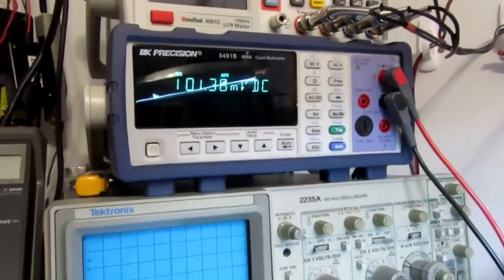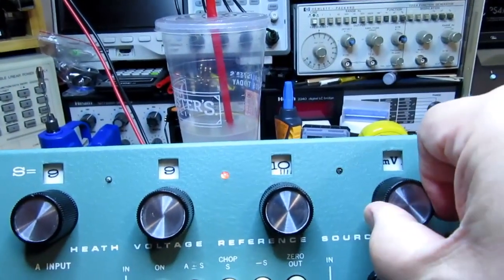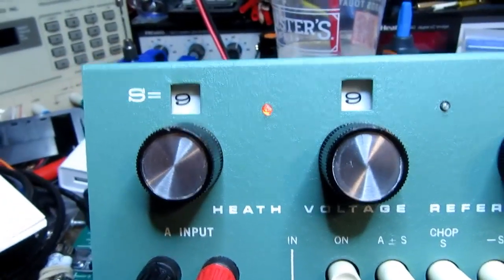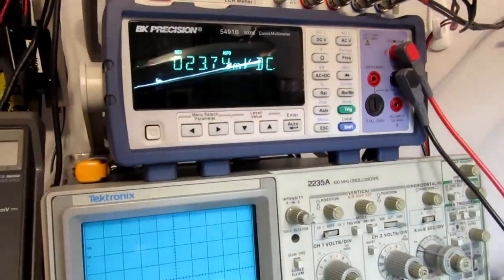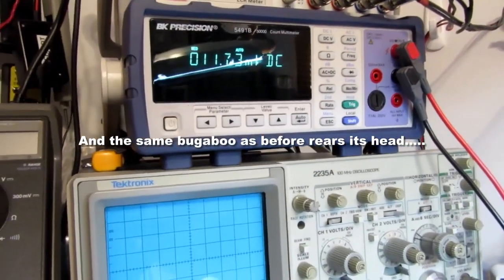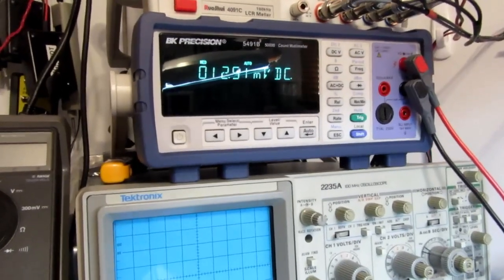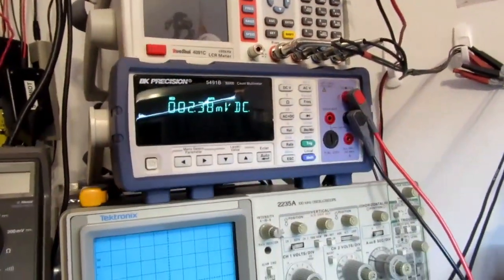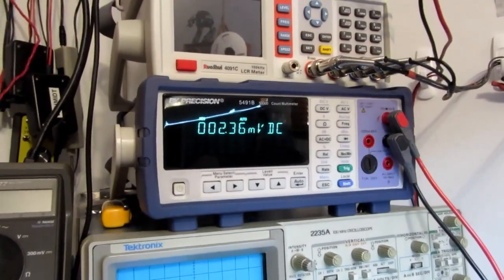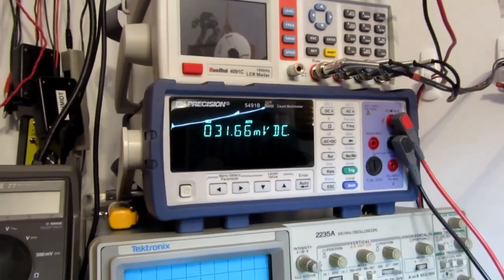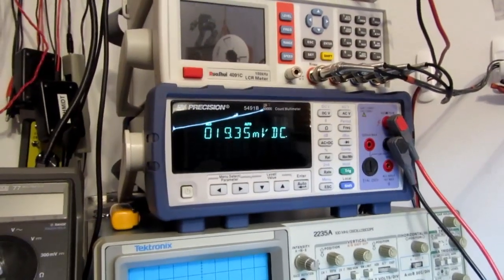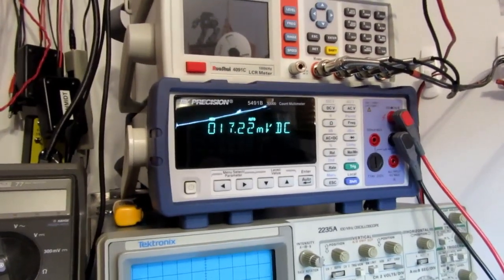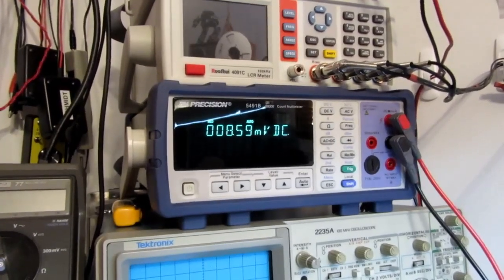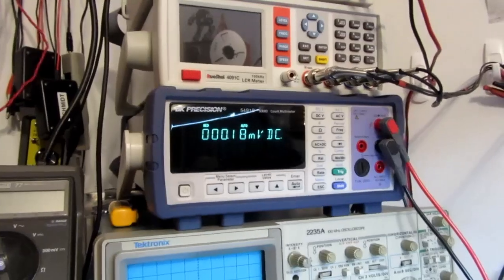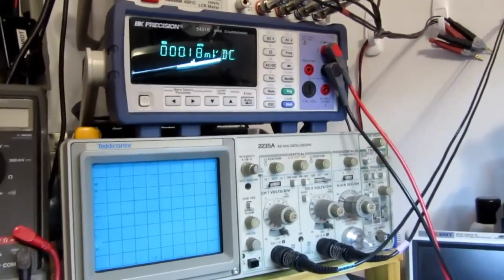I'm going to turn it one more time to the remaining range, so now it's going to be up to 10 millivolts. And again, it's off by like 1 millivolt there, reduced accuracy. I'm not getting really good results here. There's probably one resistor in there which is kind of off, and that's affecting it when it's in this lowest range.